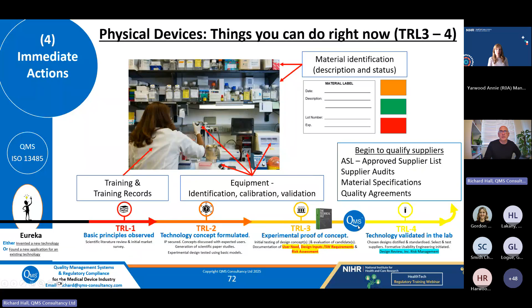Just general, easy to understand labeling is needed. Supplier qualifications: you create yourself an approved supplier list, have material specifications for the raw materials, and they could be the supplier's specifications or ones that you create. And towards the end of TRL4, it's a really good idea to start putting in place quality agreements earlier if you can. And these are quite descriptive and cover you for things like no change agreements. If you're getting a material supplied to you in a bottle, you need an agreement with the supplier, ideally, that says they will not change that without telling you in advance. And that's a requirement within the standard. So all of this goes into your quality management system and requirements, and the output of all the technical file stuff goes into your technical file.